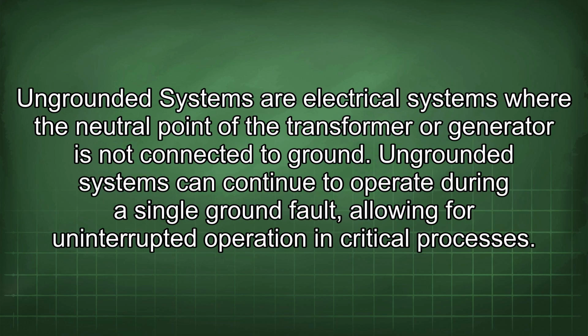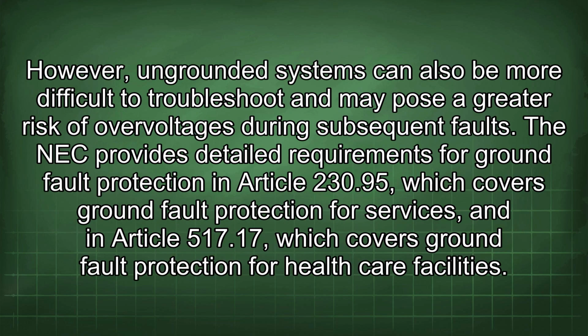Ungrounded systems are electrical systems where the neutral point of the transformer or generator is not connected to ground. Ungrounded systems can continue to operate during a single ground fault, allowing for uninterrupted operation in critical processes. However, ungrounded systems can also be more difficult to troubleshoot and may pose a greater risk of overvoltages during subsequent faults.